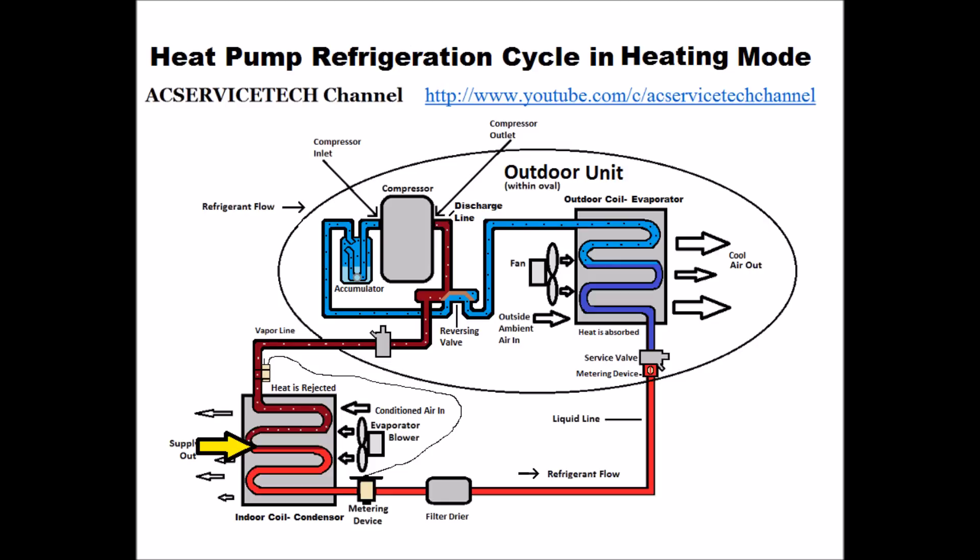It's a decent amount of that coil. It then continues to reject heat until it turns into a complete liquid — a high pressure, high temperature liquid refrigerant. The temperature decrease between the end of the saturation point and where it comes out of that indoor condenser coil is the sub-cooling.